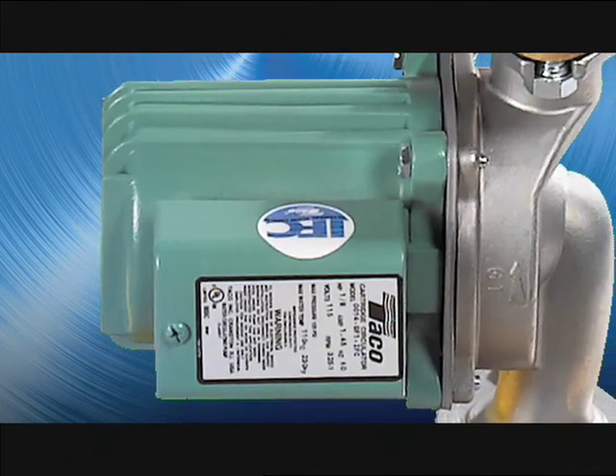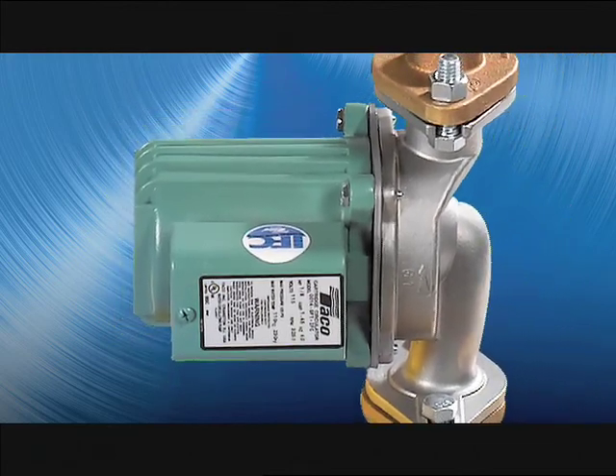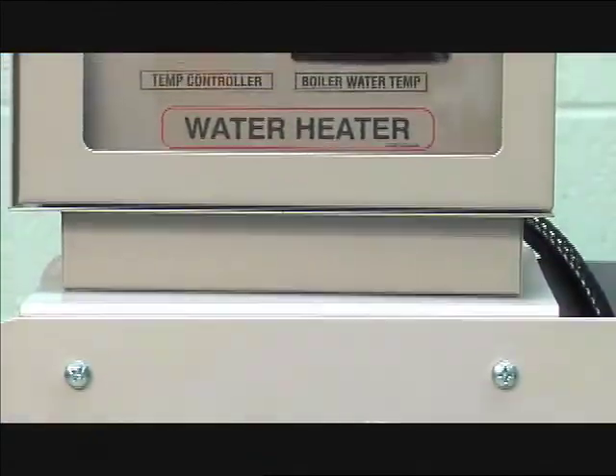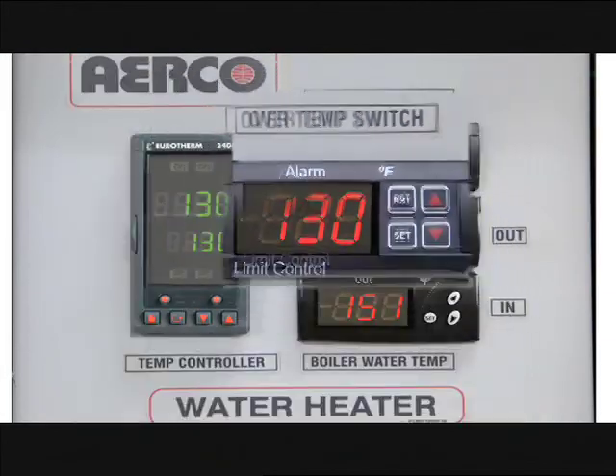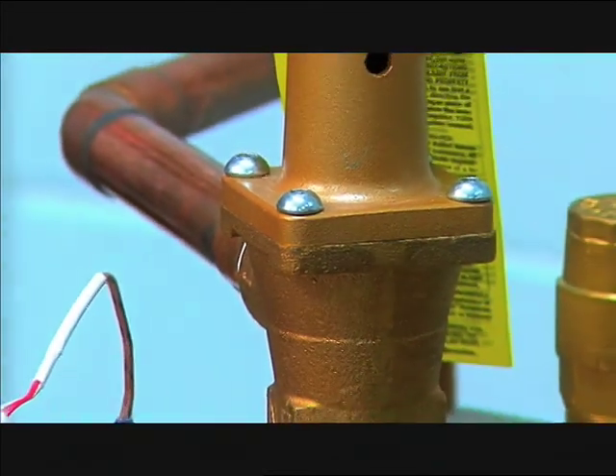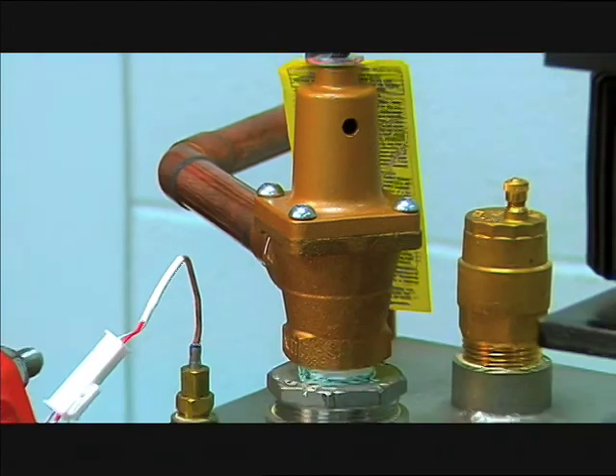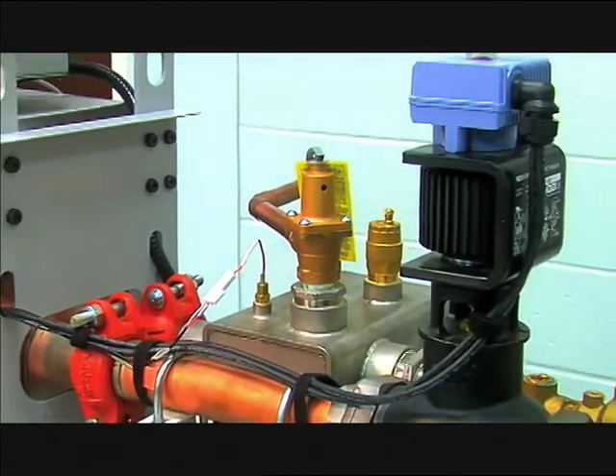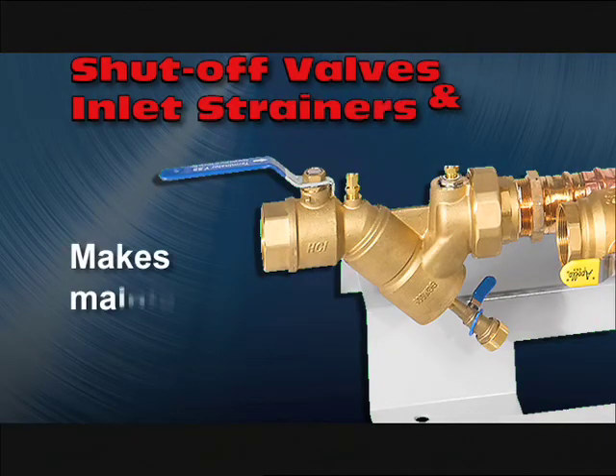The circulator and temperature sensors at the inlet and outlet provide feed-forward and feedback signals to the electronic controller that drives the unit's fast-acting control valve. Smart Plate is also designed with an over-temperature safety limit, boiler water temperature indicators, and a P&T relief valve, plus an air vent and clean-out connection that not only eliminates air but makes it easy to input a de-liming solution for cleaning.